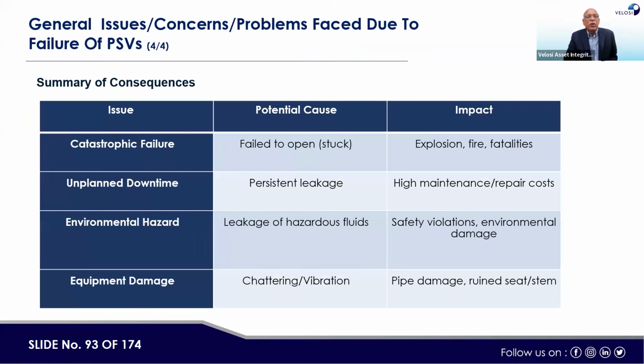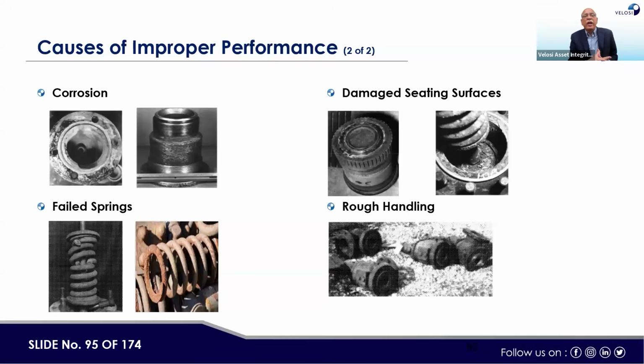So here, we are showing what it looks like when there are failures. For example, corrosion, this is the impact. Damaged seating surfaces, you can see here, and this valve will not be able to operate at the given time. And you can see all these springs are corroded due to the fluid service. Rough handling, if the valves are thrown on the ground without proper support or in a proper manner.